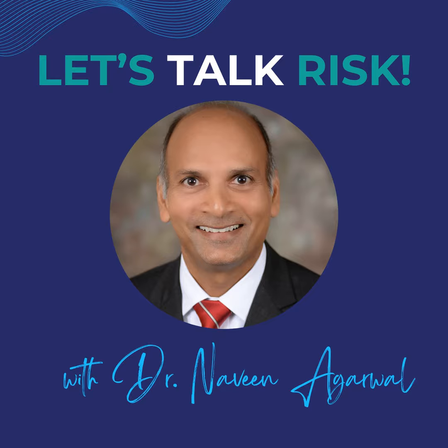Exactly. The action focused entirely on mitigation through better guidance, updating the instructions for use, the IFUs, and significantly enhancing physician training. What kind of updates? Things like explicitly stating to keep the access system valve below heart level during device exchanges, making sure the patient wasn't hypovolemic, properly hydrated, really nailing down the air purging steps. The solution was procedural control. Okay, that makes more sense. They shifted the control point to the user's workflow. Precisely. Which leads us right into this idea of the regulatory blind spot.